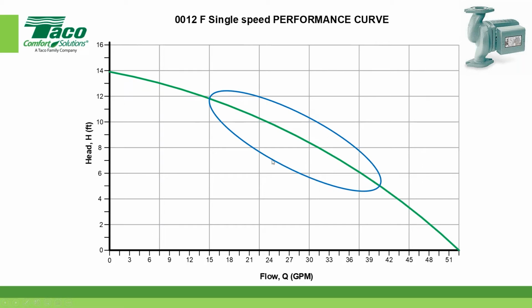I like to call this the filet mignon of the circulator performance curve, and we liken it to the middle third. The middle third of this circulator performance curve is where we want to size circulators, right there in the filet. The other thing that we want you to get out of this little session is don't size up here as an operating point, and don't size out here as an operating point. This will wear out the circulator and the motor much quicker, and this isn't any good for it either. This is worse down here because it's having to do more work, but this is not good either. So try to keep your operating points right in this middle third.